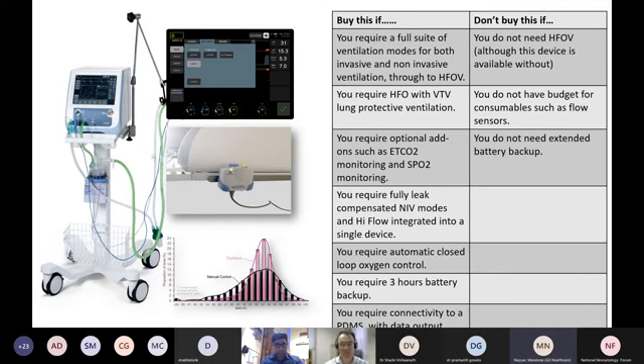And just to home in on a few of those things, on the 6,000, a main technological step was to integrate the use of devices for measuring expired CO2 in infants. This device takes a sample proximal to the patient alongside the flow sensor, analyzes it in this small box here, and gives us a breath by breath understanding of the amount of carbon dioxide present in the exhaled breath, which in turn can give us information about the quality of the ventilation, how successful ventilation is being, if that CO2 level is kept stable and is adequate.